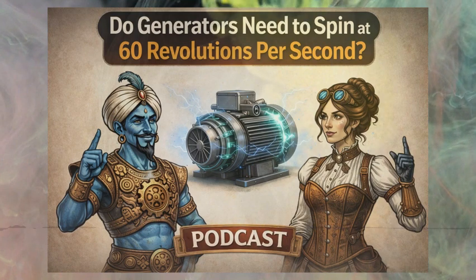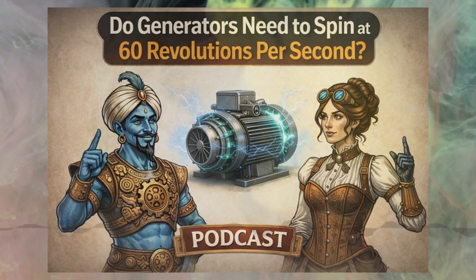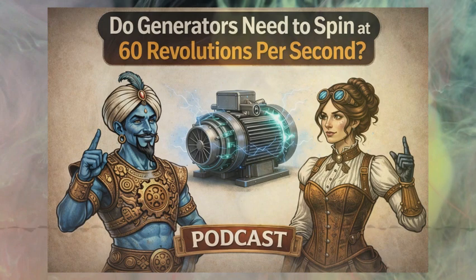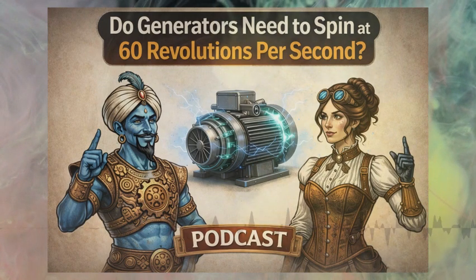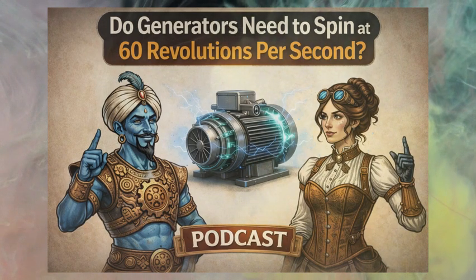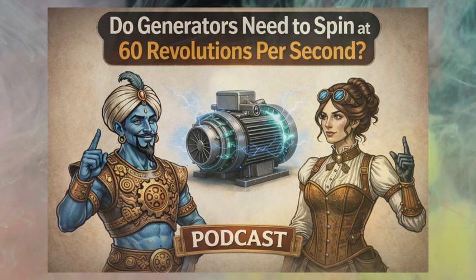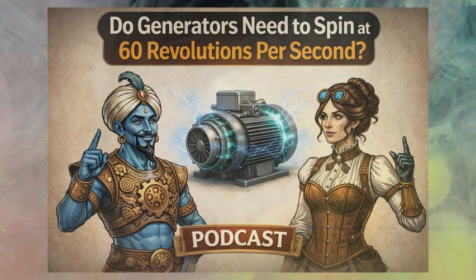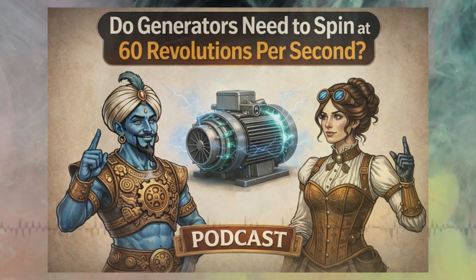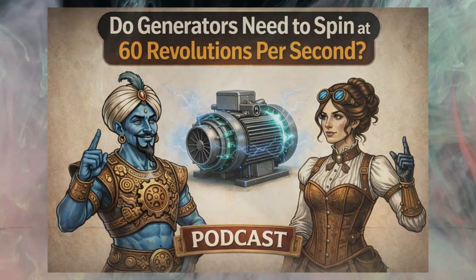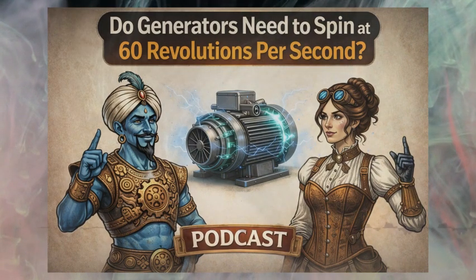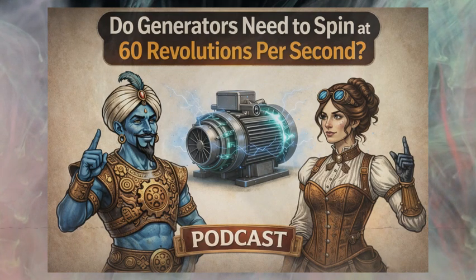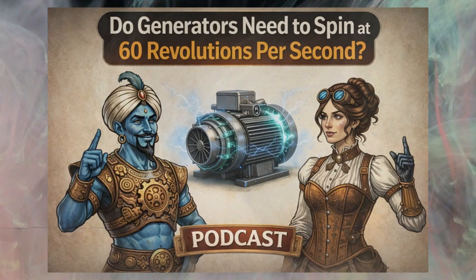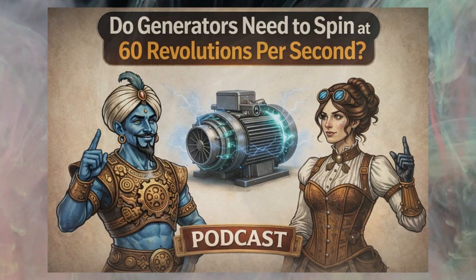So that design is basically limited to small, low-power stuff. Right, like the alternator in an old car. For the big stuff, for the grid, the industry uses the rotating field alternator. The elegant inversion, as you called it. It really is. In this design, they flip it. The armature winding, where the dangerous high voltage is generated, is now stationary. It's built into the stator frame. And the magnetic field windings, which only need low voltage DC to work, are put on the rotor.